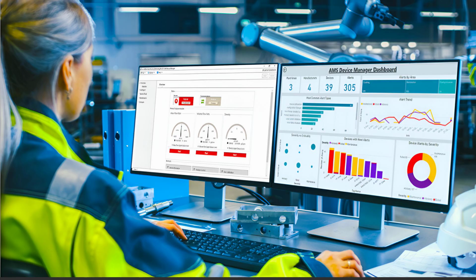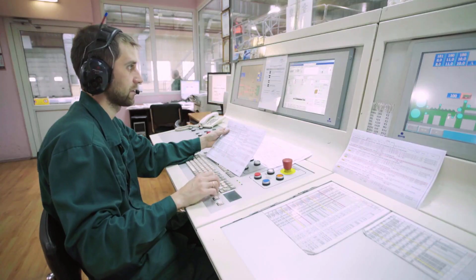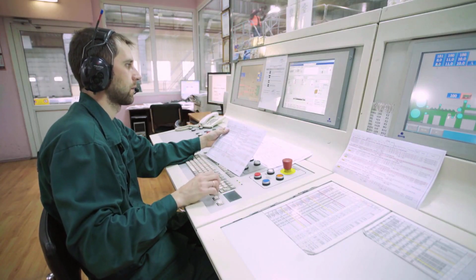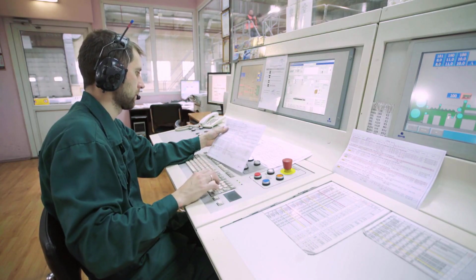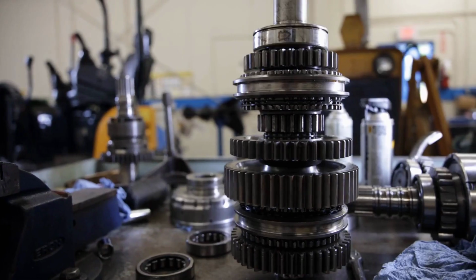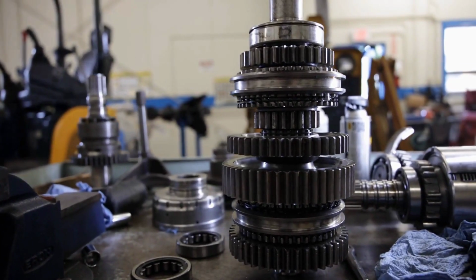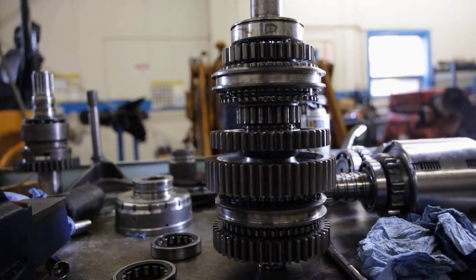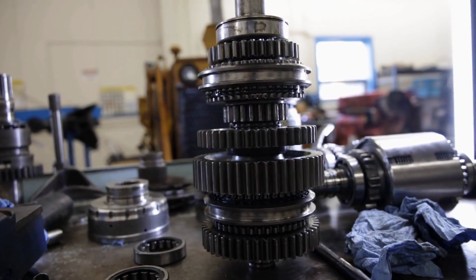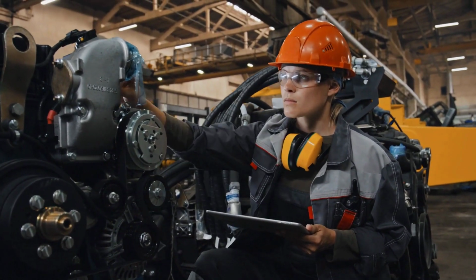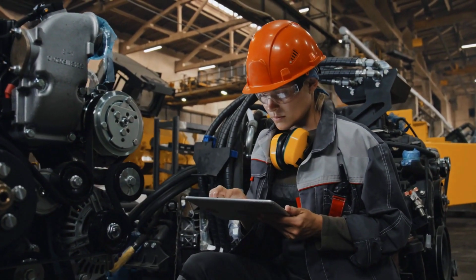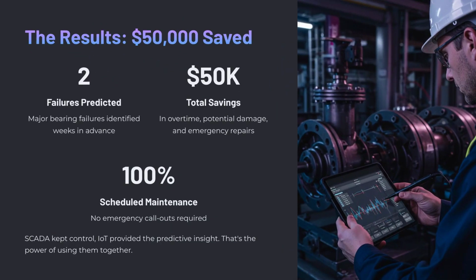If vibration crossed a preset warning level, it sent a simple digital alarm signal back to the existing SCADA RTU's input card. So, the critical high vibration warning still appeared on the main SCADA HMI screen, where operators would see and acknowledge it immediately. The result? In the first year, the IIoT devices predicted two major bearing failures weeks in advance, allowing scheduled maintenance instead of emergency callouts. Saved them roughly $50,000 in overtime, potential damage, and emergency repairs. SCADA kept control, IIoT provided the predictive insight. That's the power of using them together.